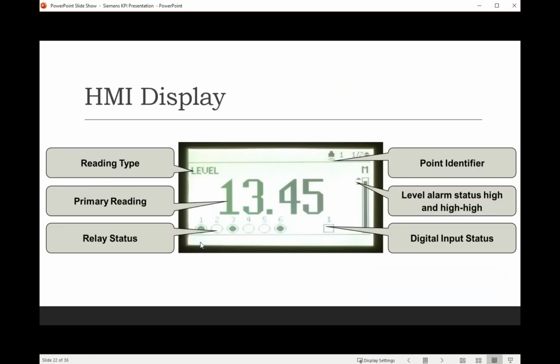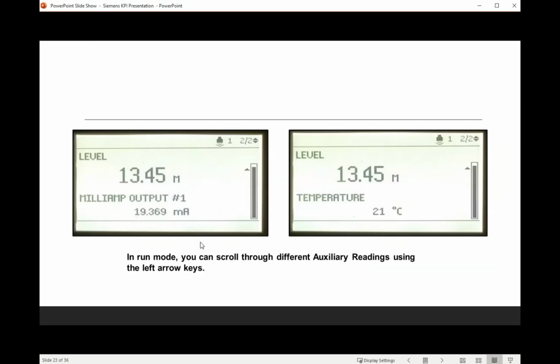So this is the basic display of the new Hydroranger. You got your reading type, your level, all your relay status at the bottom. Your 0 to 100% scale on the right of this secondary screen. So that's the main screen, but if you hit the bottom key and go down to the secondary screen, it comes up like this. You've got your main reading, and then you have an auxiliary reading at the bottom.